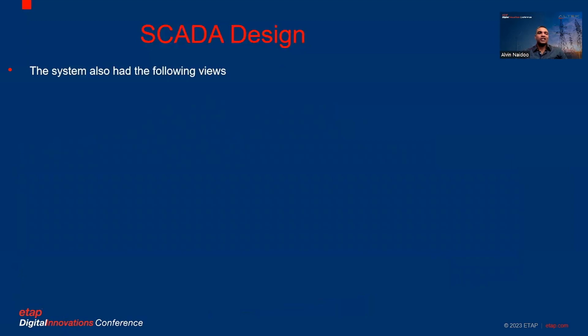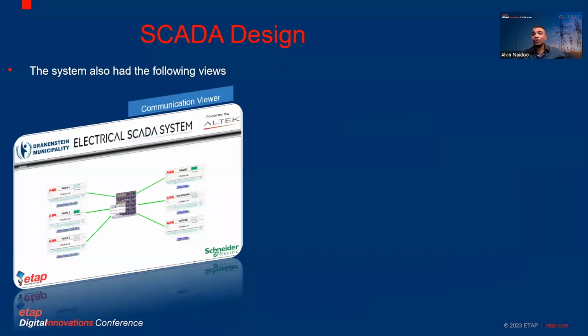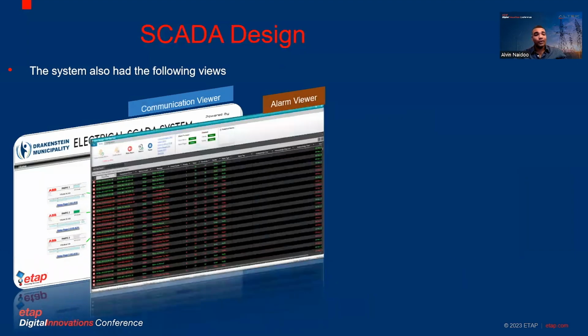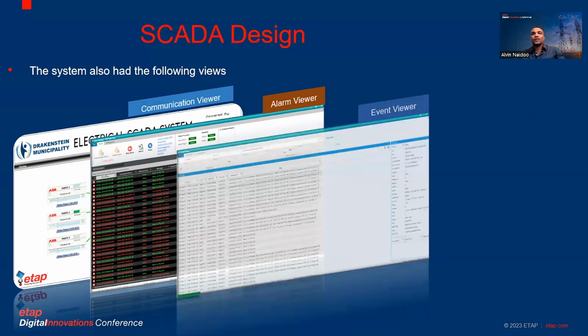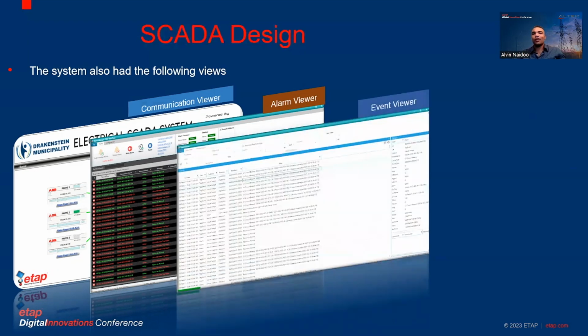So coupled with these interfaces were particular viewing pages as well. Aside from your conventional substation viewing page and layout, we also created a communication viewer to basically view communication coming through from your RTUs and the health statuses of your particular RTUs. We created an alarm viewer for the customer. And with the alarm viewer, the customer was involved with us on the priority levels and the optimization levels of these particular alarms. Your event viewer, also the customer was involved with us for programming the various points and the events that we view.